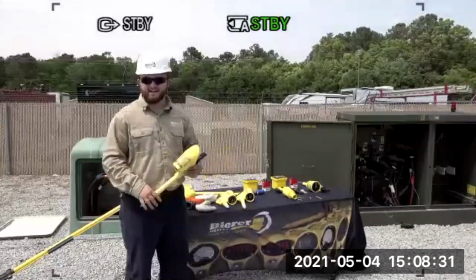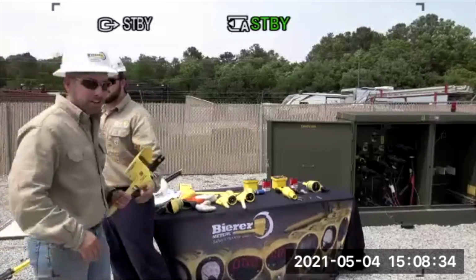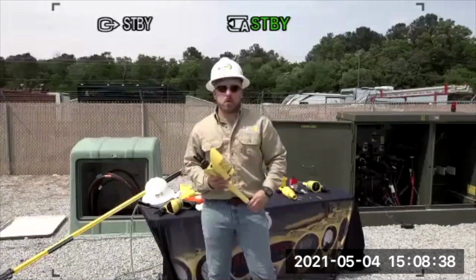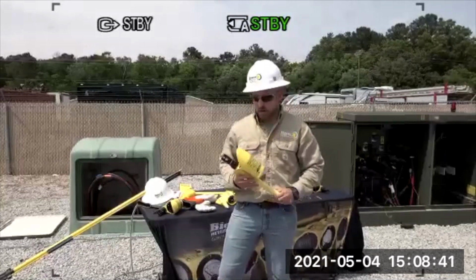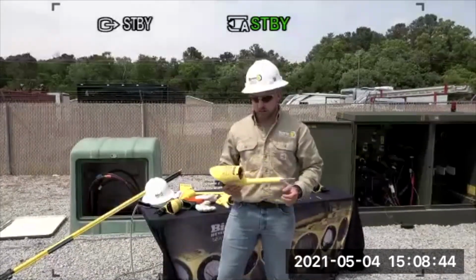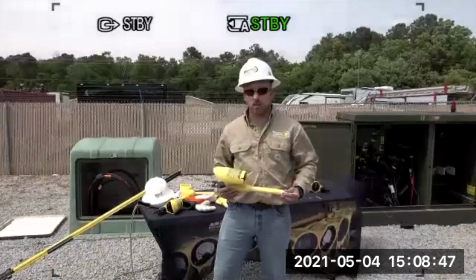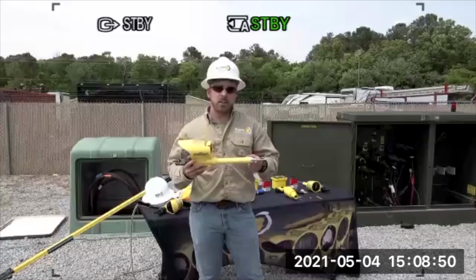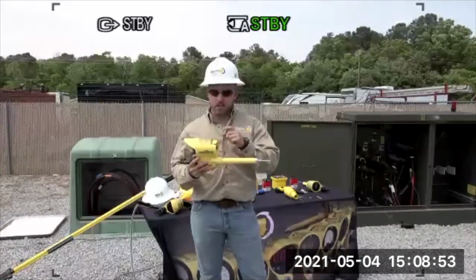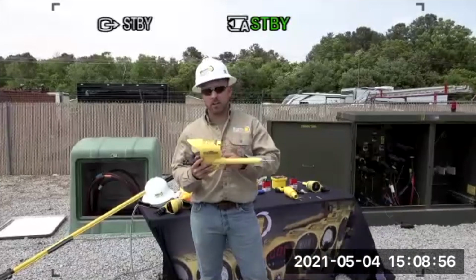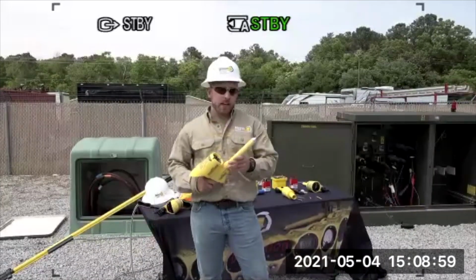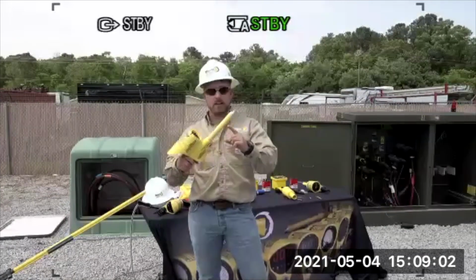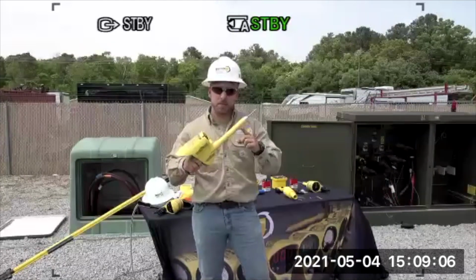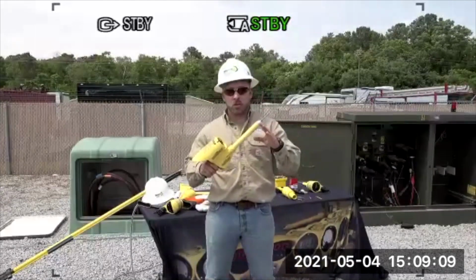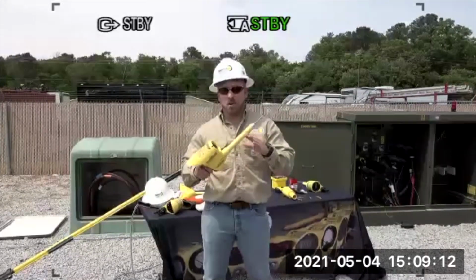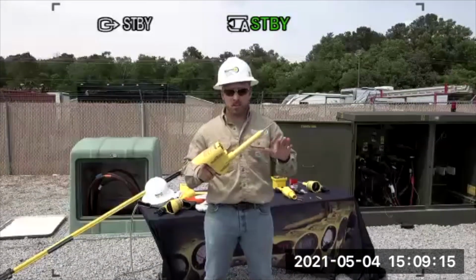I'm Parker Height. Regardless of manufacturer, when you have a voltage detector, the functionality is that these tools make contact with conductors, the meter couples with the capacitance, and the conductive components inside look at the current in relation to the ground plane. We also have a line about 2.5 inches down from the tip of the probe, which indicates where you do not pass with an energized conductor or any conductor at all, whether it's ground or anything like that.